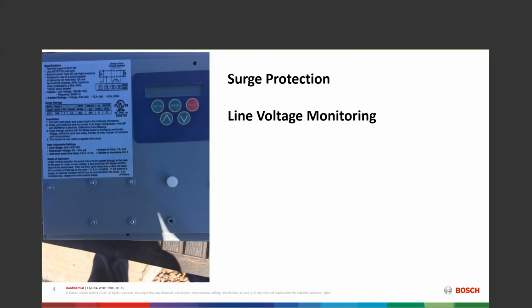The next thing is you're not going to see this in the IOM, but you'll always hear it in training, and it's a surge protection device. Don't really care what brand, but that board on my unit has to and needs to be protected. Somebody says, well, Fred, how come you don't just put it into the machine? Just not happening at this point in time. So we're asking you to install a surge protection type device. Some devices are maybe more economical than others. Some devices may do more things than just be a one and done type scenario.